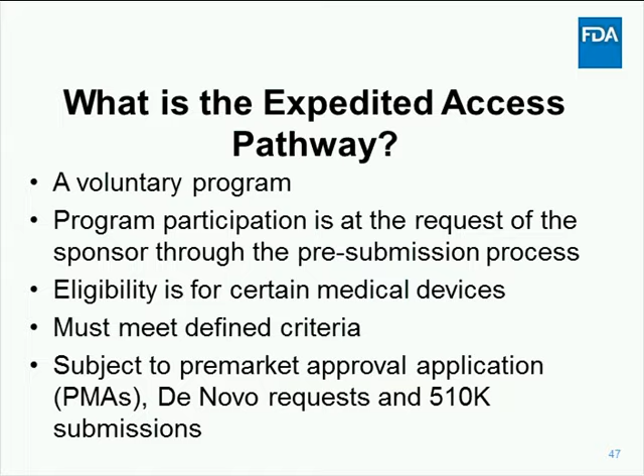Program eligibility is not for all medical devices. There is a defined program criteria that must be met for the pre-submission to receive an EAP designation. This criteria will be discussed further in the next few slides. If an EAP designation is granted during the pre-submission process, please be aware that this designation will follow the application submission throughout the review process. Applications eligible to qualify for the EAP program are premarket approval applications, also known as PMAs, de novo requests, and 510(k) submissions.